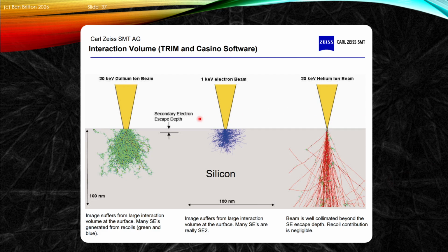Now, why would you want to change your source types? Well, you might want to, for instance, improve your spatial resolution. So gallium FIB can produce effectively a 30 kV beam, and has a relatively wide probe. It's high energy, so these ions go quite deep into the sample and create lots of damage and interaction. If you drop the voltage, you can make the probe smaller and interaction smaller. But if you want a really narrow and high spatial resolution, you can improve this by having that very, very narrow source, where we have the 0.35 nanometer source, that can improve the spatial resolution even further.